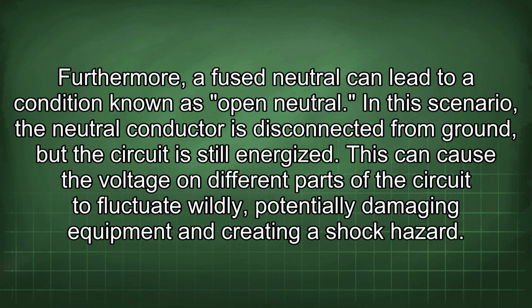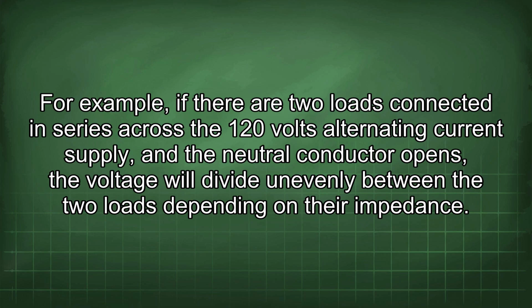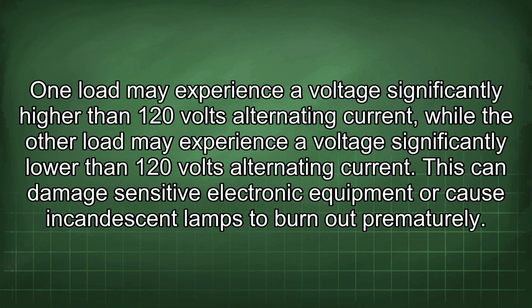For example, if there are two loads connected in series across the 120 volts alternating current supply and the neutral conductor opens, the voltage will divide unevenly between the two loads depending on their impedance. One load may experience a voltage significantly higher than 120 volts alternating current, while the other load may experience a voltage significantly lower than 120 volts alternating current. This can damage sensitive electronic equipment or cause incandescent lamps to burn out prematurely.